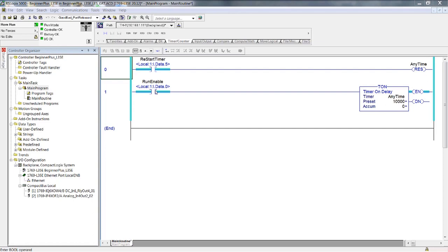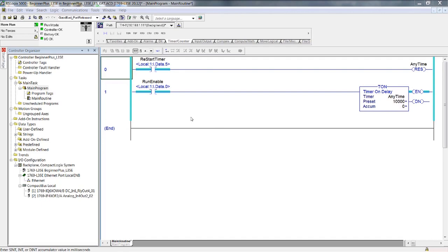I gave you yes, no, or maybe for choices. I circled maybe. Enable for one scan — remember, last man wins. This resets the timer; this one enables it. So for one program scan, this instruction is enabled — but literally a microsecond later, you're at the end of the logic, back to the beginning, and it's reset again. So it is never true for one thousandth of a second. We still don't know if it's really timing or not.